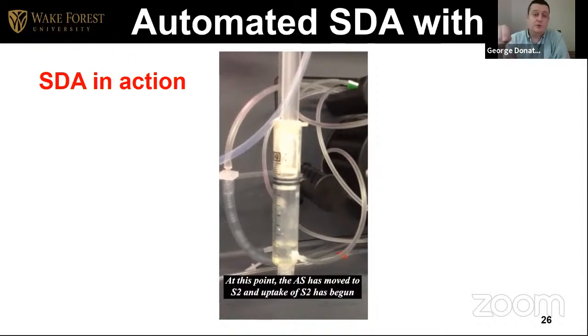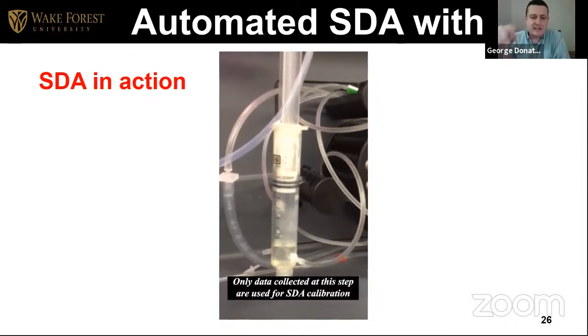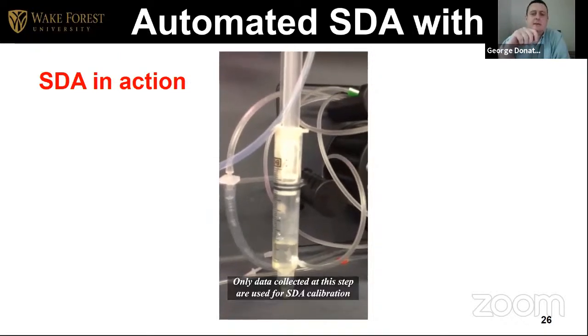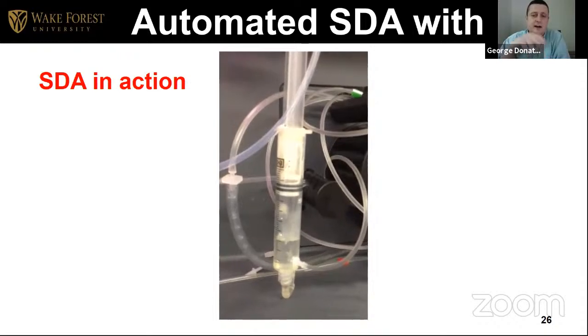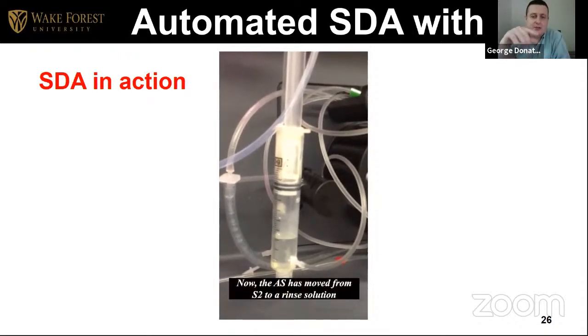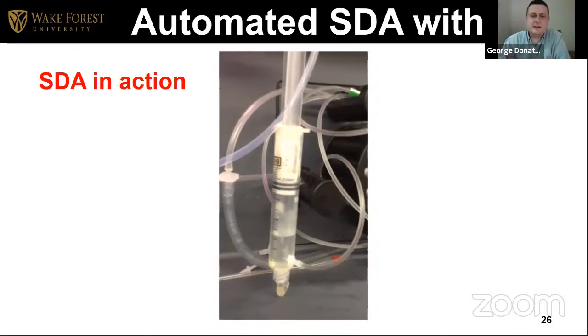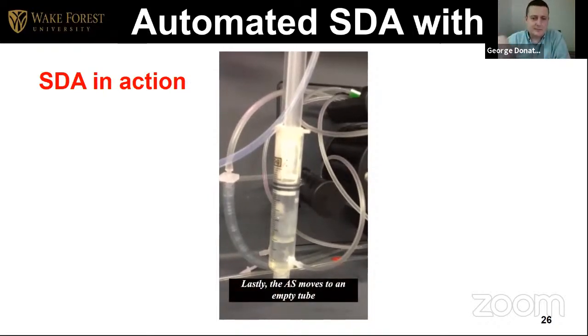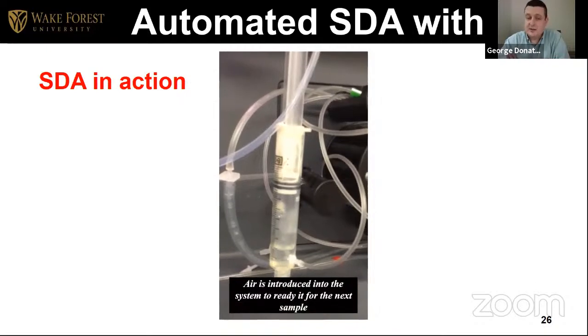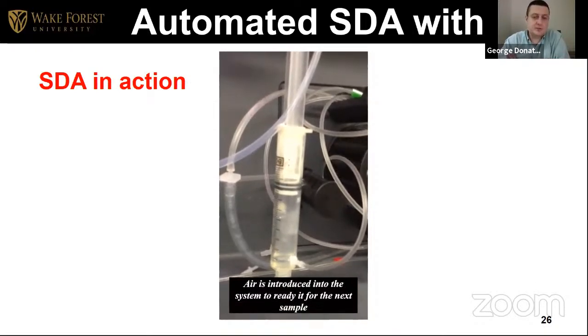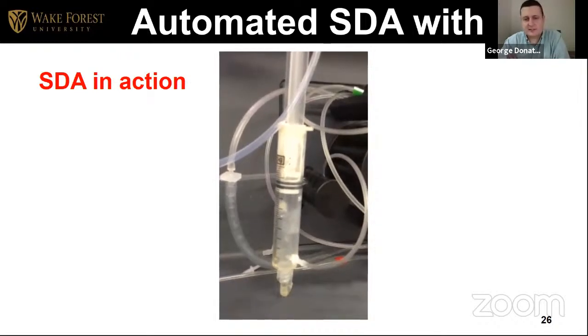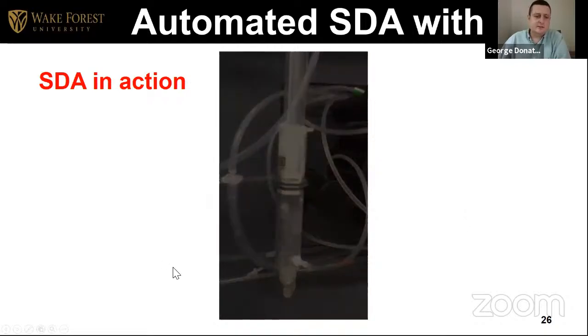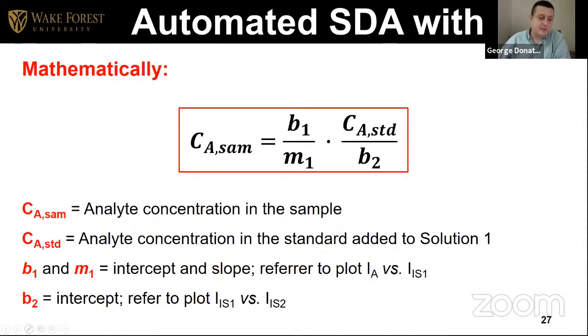Then the autosampler will move to the second solution, and that second solution comes in, starts mixing, and goes to the ICP, in this case an ICP OES. After all the measurement is done, you just move to a rinse solution to make sure you clean the tubing. Again, this is all automatic, it's all set up in the autosampler software. You just need to put the solutions there. Then finally, you need to clean up, get rid of that solution, so it moves to an empty tube to introduce air and clean up the whole syringe. Once that happens, you can move again to the next sample and start the sequence again. So that is generally what happens with the SDA in terms of automatic setup.